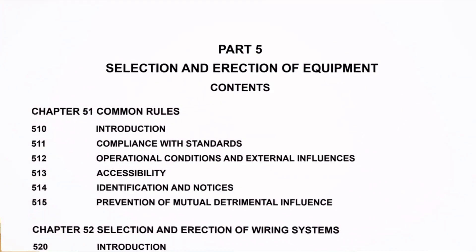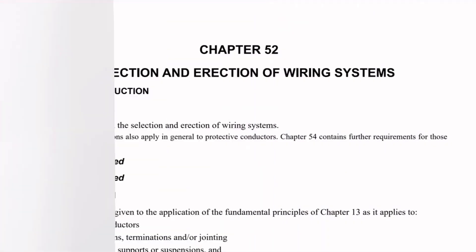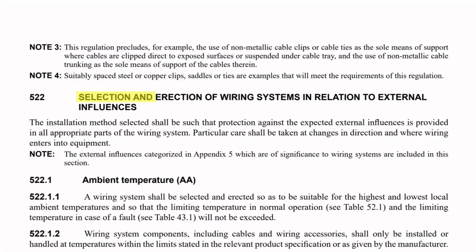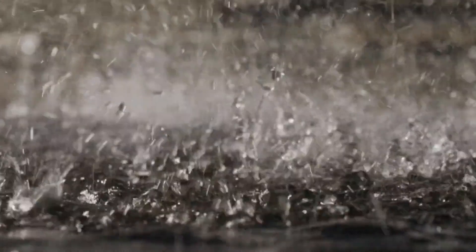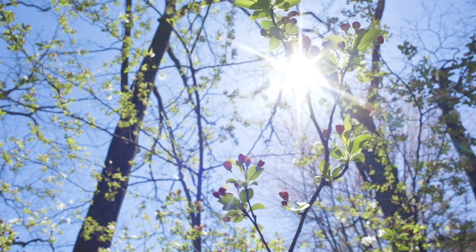Part 5 of BS 7671 covers the selection and erection of equipment. Chapter 52 refers to wiring systems in particular, and in regulation group 522 we find the heading 'selection and erection of wiring systems in relation to external influences.' This group of regulations is broken down into a number of areas covering different things that can negatively affect wiring systems once they're installed.